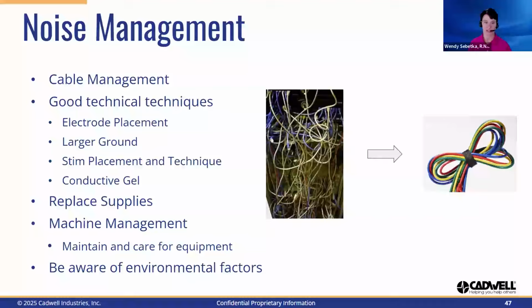Using filters such as a 60 Hz notch filter will reduce or eliminate 60 Hz interference when all other options have failed. The use of a noise detect probe may be helpful in locating the source of the noise, providing further information for how to minimize the effects. Adhering to the manufacturer's recommendations for maintenance and care of the equipment will provide successful long-term operation of your device.